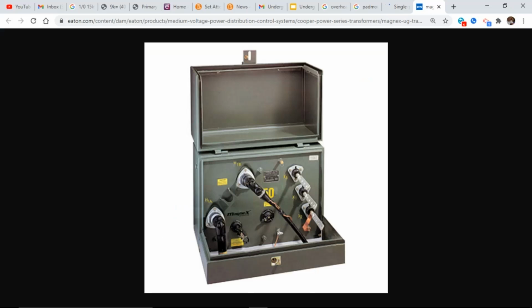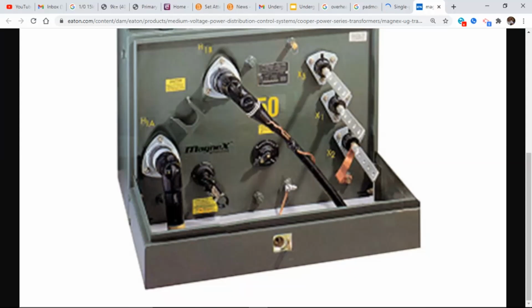Now, when you're constructing your transformer, and you notice the single phase transformers that we had out there in the field, you're going to want to loop just a little bit of extra cable down here in the bottom. You'll notice right here this is covered in this area, but sometimes you'll see the wire come up and make a loop and then come into the transformer like this. The same thing on the bottom. You want to give a little bit of extra. Failure points are obviously going to be inside the elbow, and if the elbow fails, all you have to do is pull that little bit of slack back up and reinstall a new elbow. If this area, which is covered by the PVC jacket, makes contact with the secondary bar, that is not insulated, so you would get a large flash right there. Just make sure you understand that the outer jacket is not insulated.